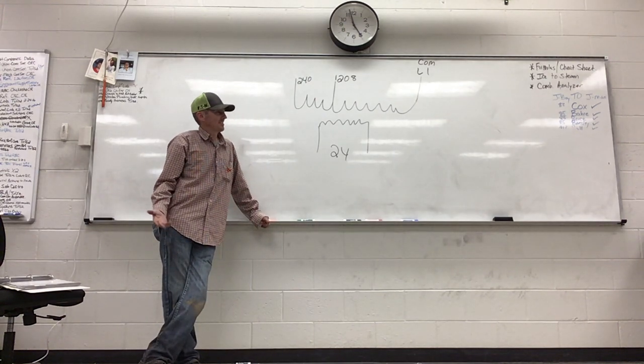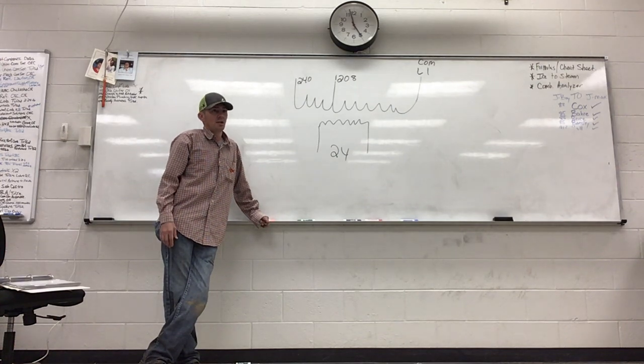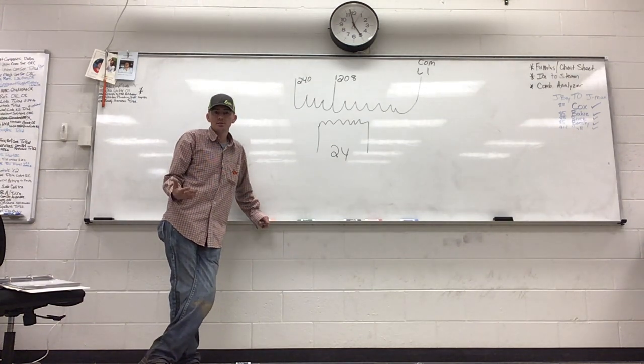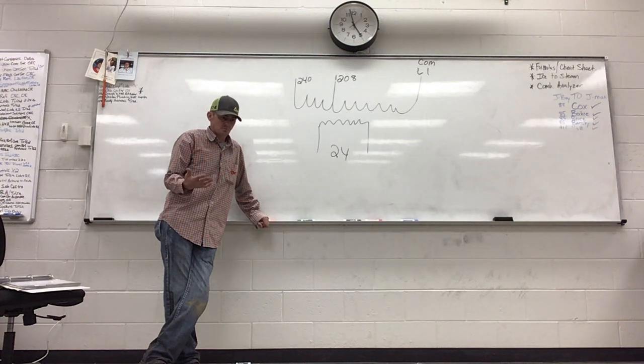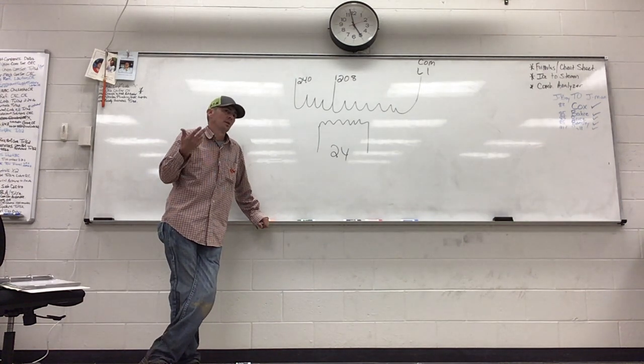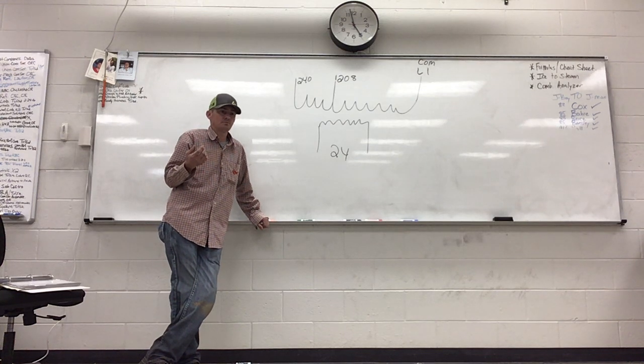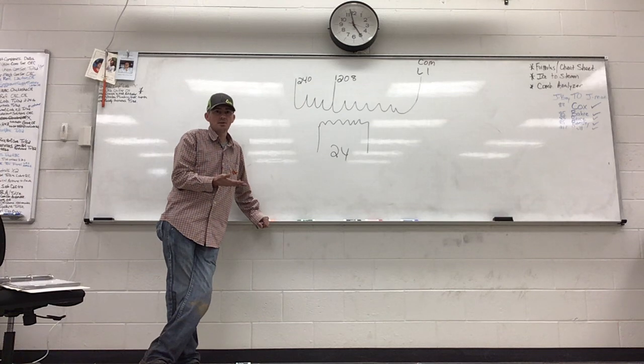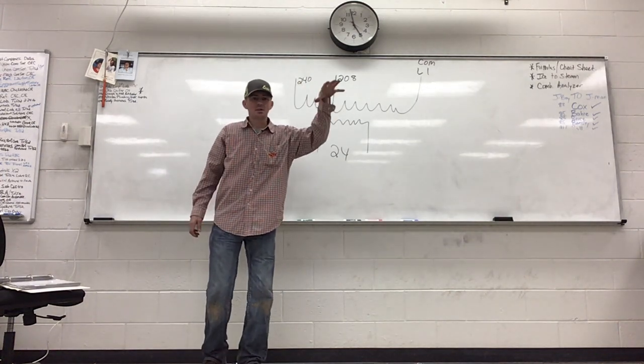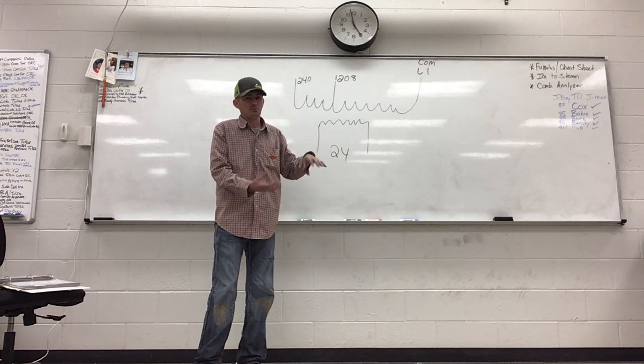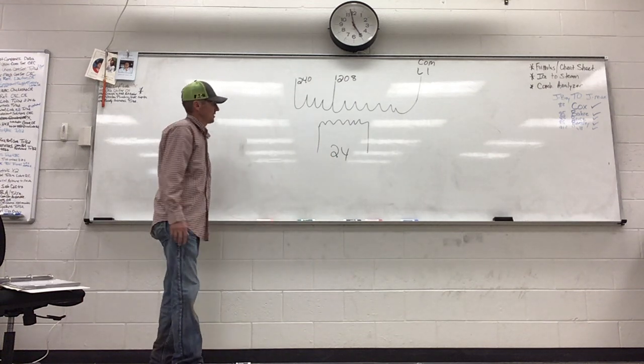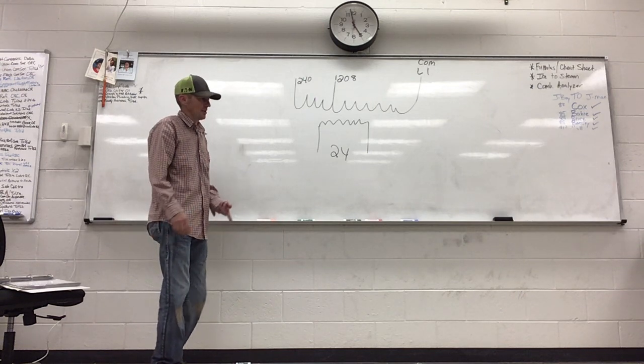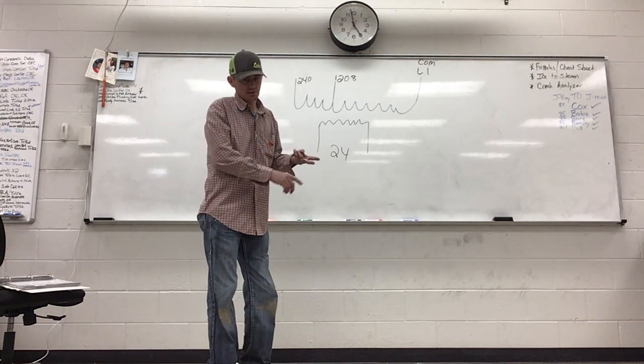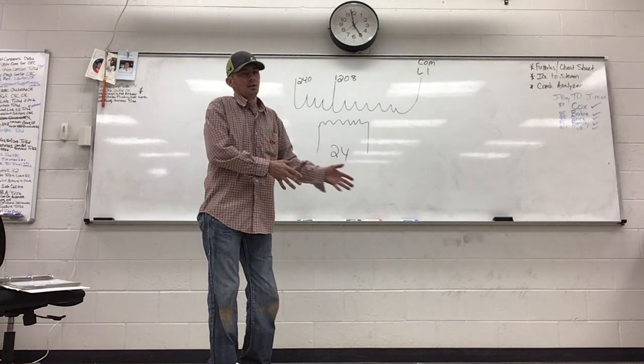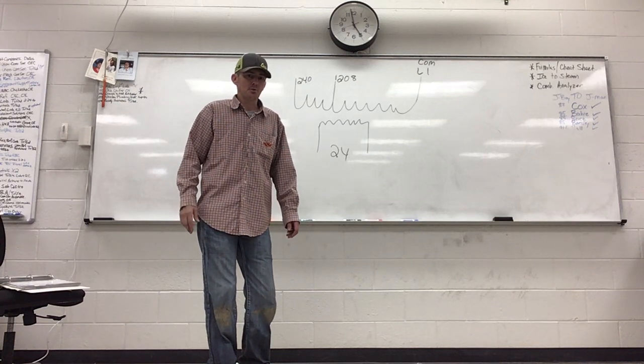The other thing, I'm just going through inspections in my head, but all of our newer rooftop equipment, everything's more efficient now, right? The SEER rating's gone up, our efficiency's gone way up. And so if you're pulling off a 20-ton rooftop unit and its maximum fuse size is 100, and you put another rooftop unit the same size right in its place, and you look at its maximum fuse size, they're always smaller. So make sure you fuse down the disconnect. When I do a startup, I guess that's the first two things I check. What's the maximum fuse size? What's in the disconnect? Make sure the fuses match, because if they didn't change them, there's still the big fuses for the old inefficient unit.